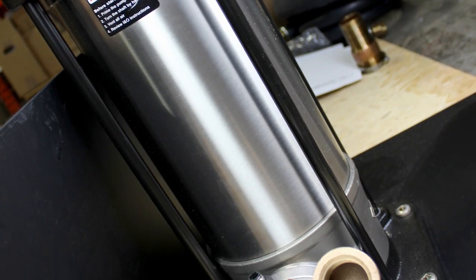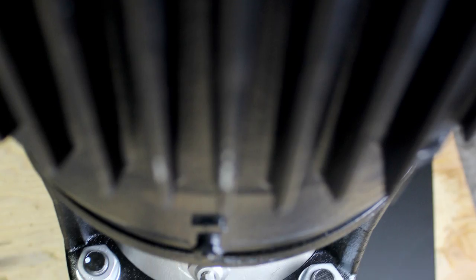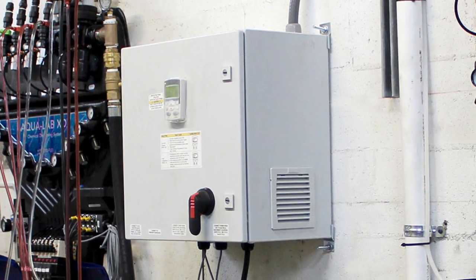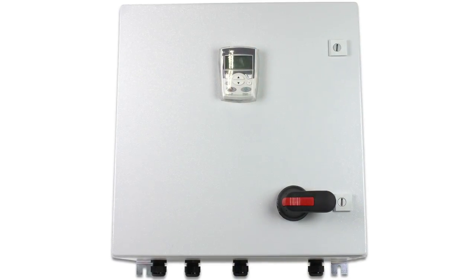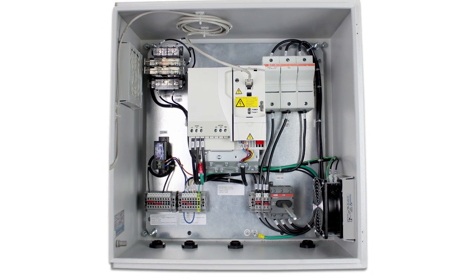You can also upgrade to our floor mounted 20 or 40 GPM Grundfos pumps. These vertical centrifugal multi-stage pump systems are designed with stainless steel impellers, totally enclosed fan-cooled motors, and higher temperature thresholds for longer life and less maintenance. The pump motors are controlled by variable frequency drives, also known as VFDs. VFDs adjust the speed of the motor based on real-time site demands and system flow requirements, reducing related energy consumption and costs. VFDs will also extend the life of the pump to reduce wear and tear on the motor and allow cooler running pumps due to not bypassing water.